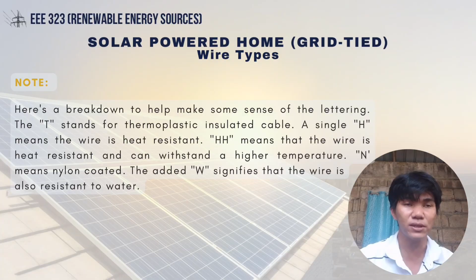So PV wires. This type is an exclusive kind of wire created for PV applications. These cables behave extremely well in very hot temperatures and other harsh environmental conditions. Its special characteristics compared to other wires is its insulation and outer shell, which is made up of XLPE or EPR. XLPE is an acronym for cross-linked polyethylene, a thermosetting polymer, meaning that the material polyethylene (PE) is cured under heat. In that process, it forms bonds in all directions, forming a three-dimensional matrix. EPR means ethylene propylene rubber. So these are its parts: the flexible thin copper, XLPE insulation, and XLPE outer sheath.